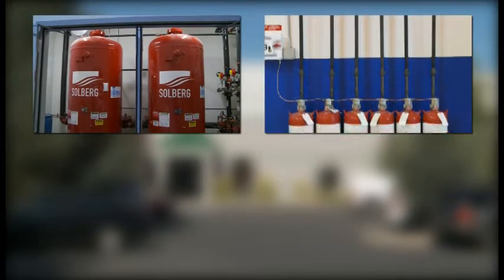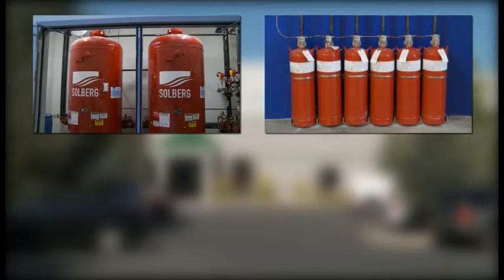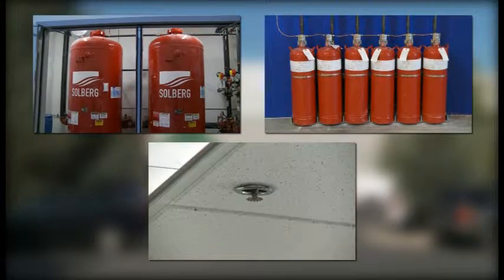Systems include an AFFF, aqueous film forming foam, alcohol-resistant fire suppression system for the flammable liquid storage area, an ABC dry chemical suppression system for the water-reactive flammable solids room, and wet pipe sprinkler system protection in other areas. The existing part of the facility is equipped with an ESFR, Early Suppression Fast Response Fire Sprinkler System.